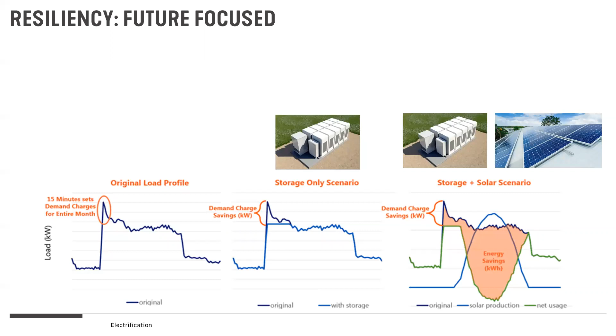So electrification plus storage gives us the resilience and flexibility we're looking for in our buildings. The nice thing is, because that same system can provide demand charge manipulation, it can also provide a really positive cash flow for the entire year. We typically see returns on investment for microgrids now at less than 10 years, which is phenomenal — and that's just from manipulating the demand charge, not even counting the reduced cost of power. So that same system, for 99% of the year, gives you a great financial return, and in the event of an emergency, gives you that resilience — preparedness for emergency shutoffs, and extra capacity if the whole world is burning down.